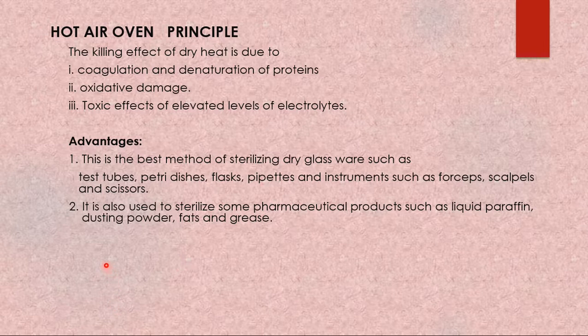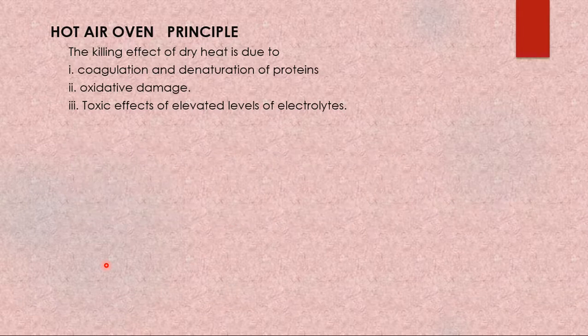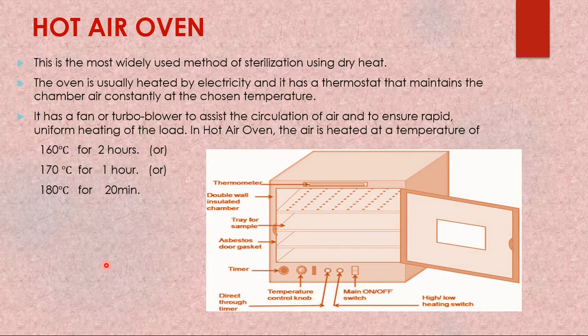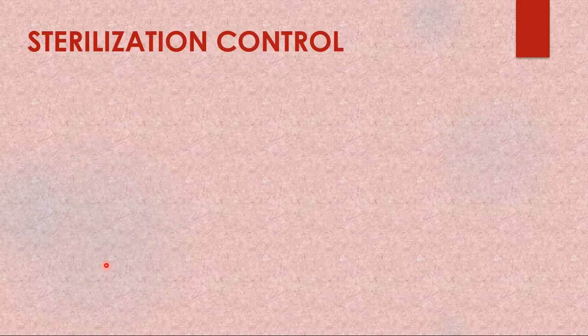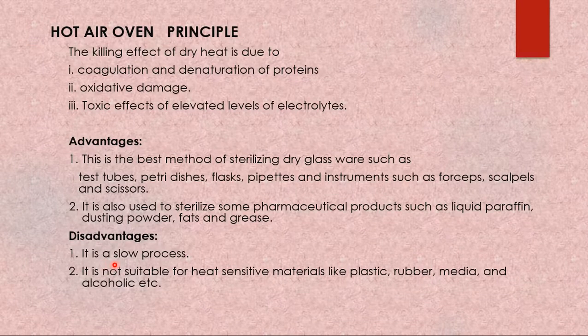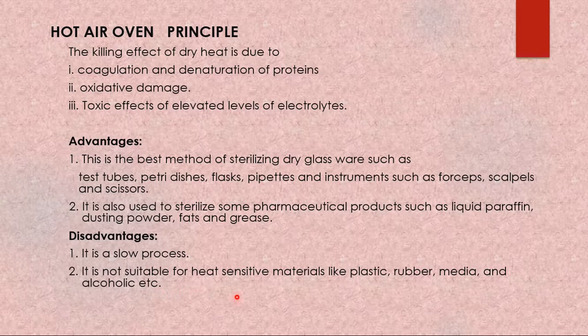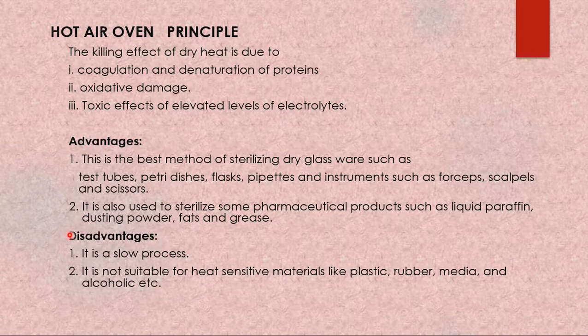The main disadvantage of the hot air oven is that it is a very slow process — it takes hours. It is also not suitable for heat-sensitive materials like plastic, rubber, culture media, and alcoholic substances. So glassware and metal instruments are ideal, but plastics, rubber, and media cannot be sterilized this way.